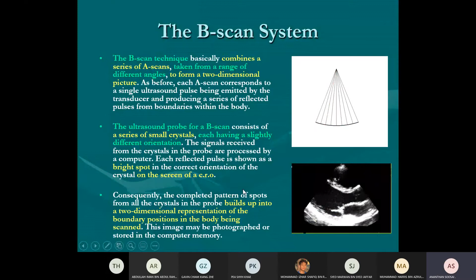A 2D image. The B scan technique combines a series of A scans taken from a range of different angles to form a two-dimensional picture. This is a very good term you need to remember. B scan technique basically combines a series of A scan images to form a two-dimensional picture. Okay, the example for B scan is a series of small crystals, each having a slightly different orientation. The signal received from the crystal, each reflected pulse, is shown as a bright spot on the screen.